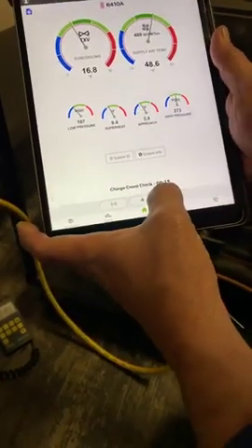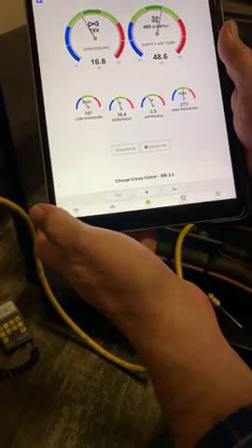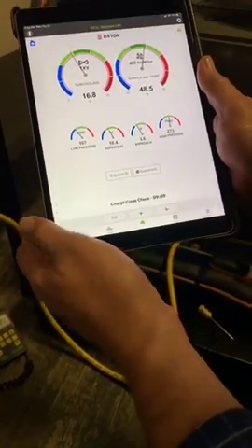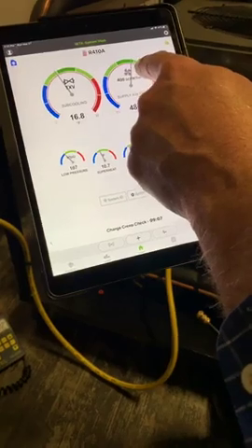And what this is going to do is run down, and I don't have to run the full 10 minutes here before we cut off this video, but at the end of 10 minutes, it's going to make sure that the airflow is in the correct range. So you see that's getting in a dark green range now, and that the subcooling is in the correct range.